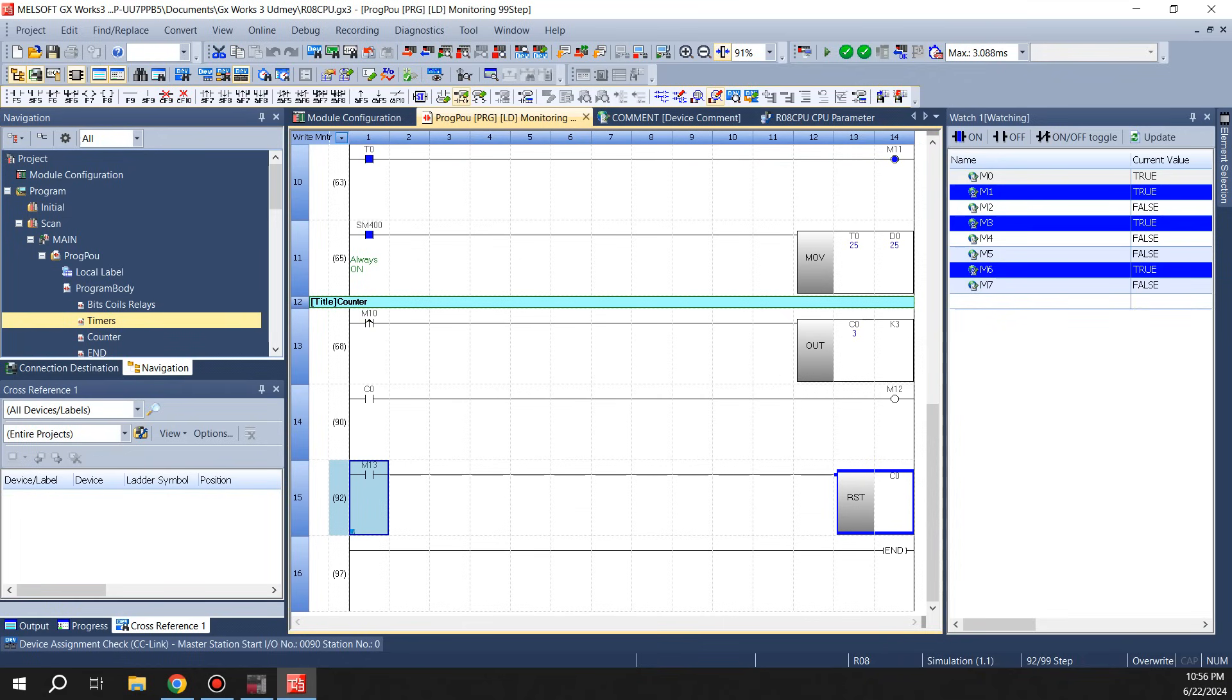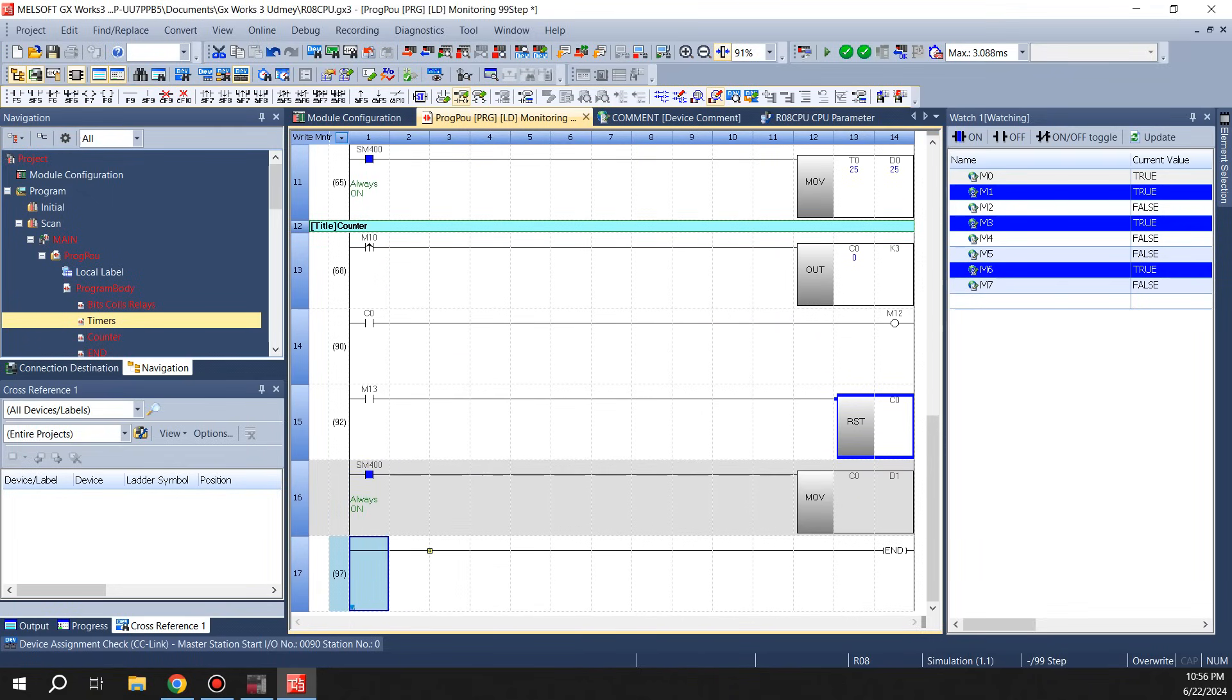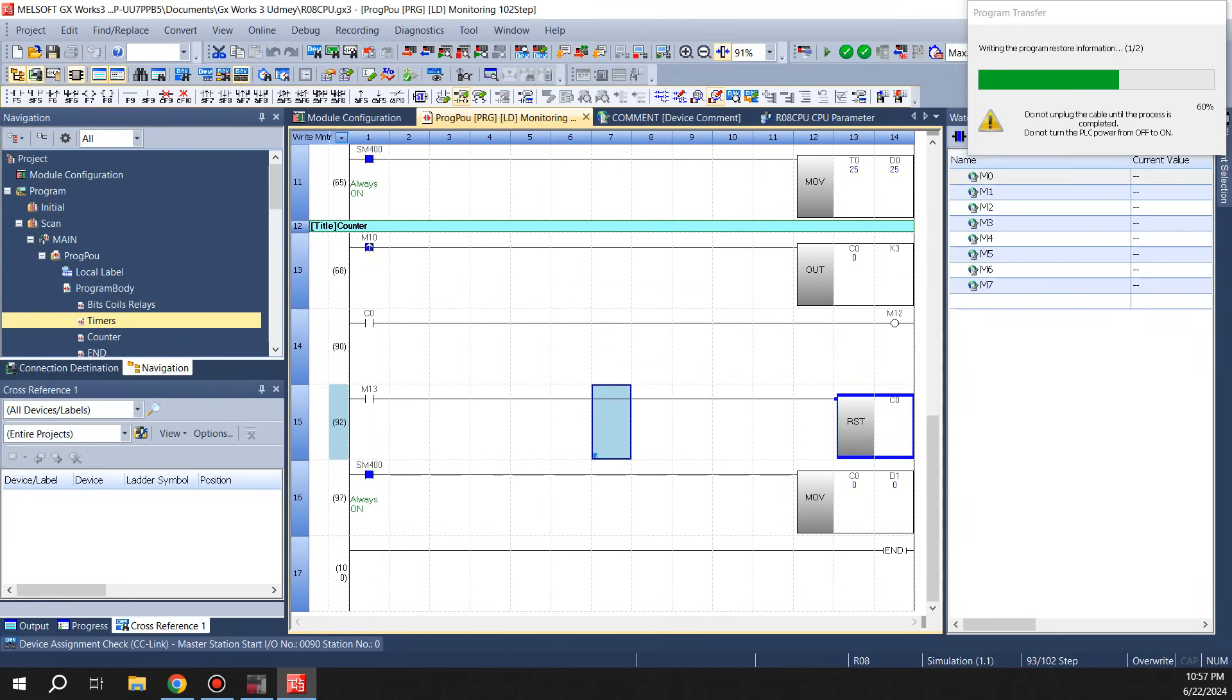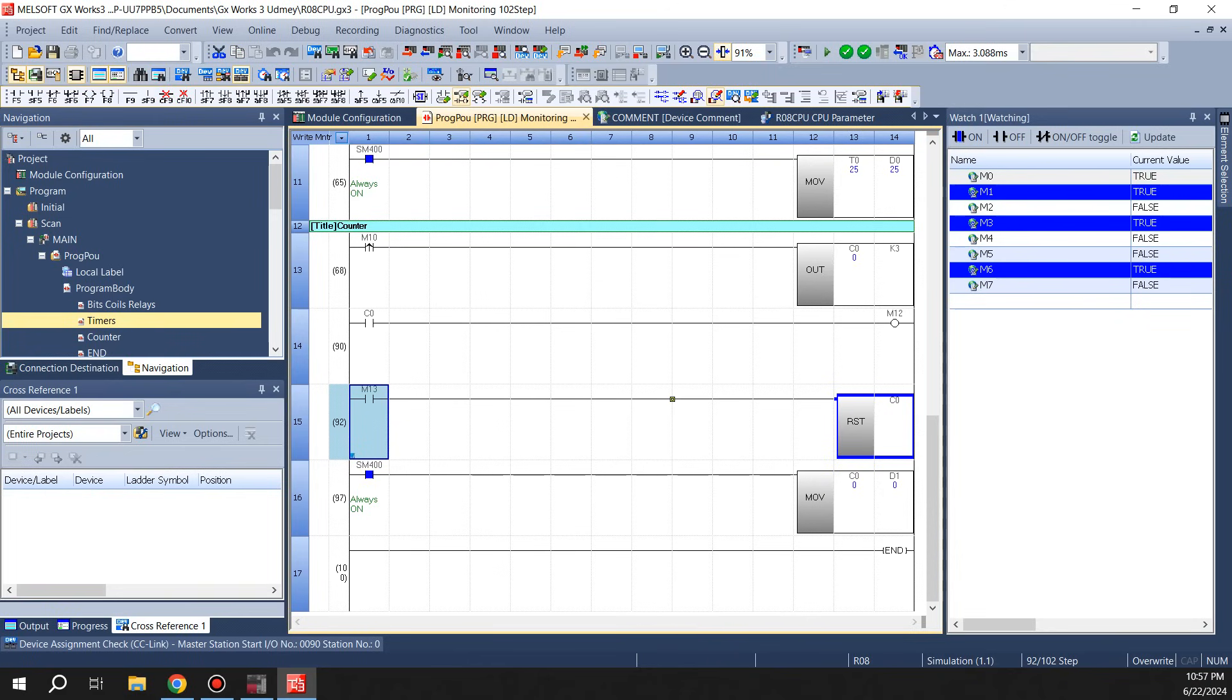You could toggle this and reset the timer. So that's how easy timers are in Mitsubishi. And you can also move the counter value similarly like the timer. So we come down here, SM400, move C0 D1. So now you would move your counter value to the D register and you can use that to program or compare stuff. So let's do it again, one, two and three. Now we can come back and reset which is zeroed out. So that's how counters work in Mitsubishi IQR. I'll see you in the next lecture.